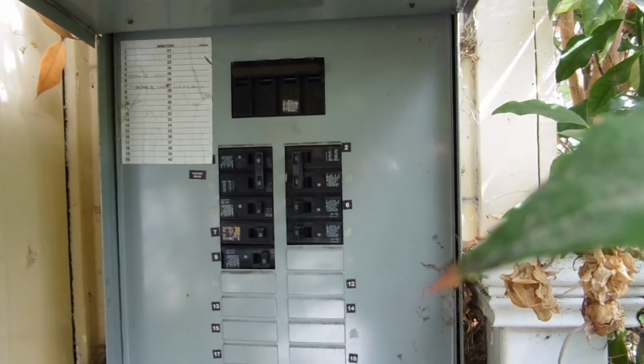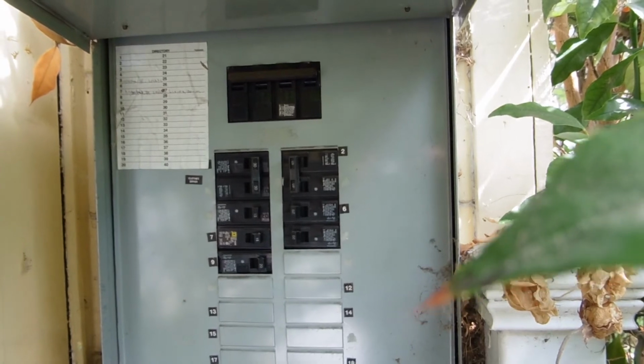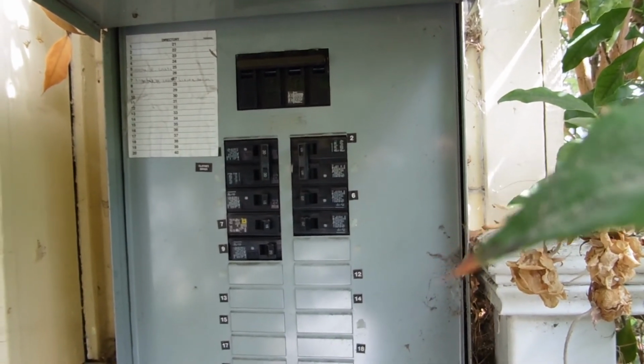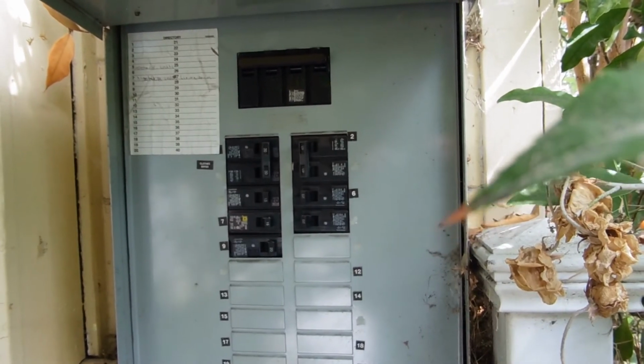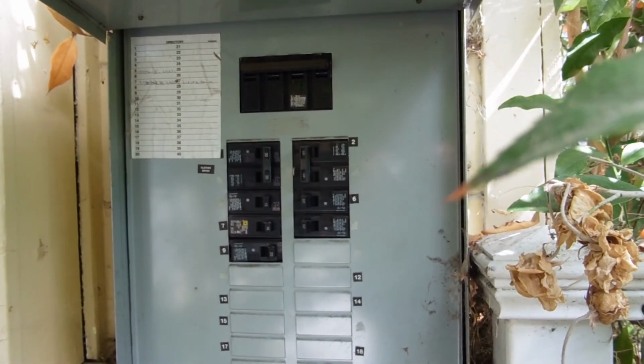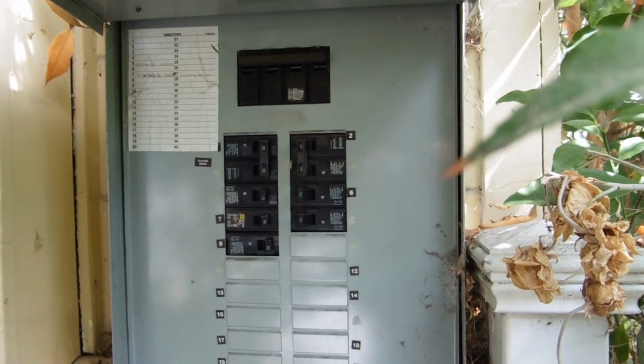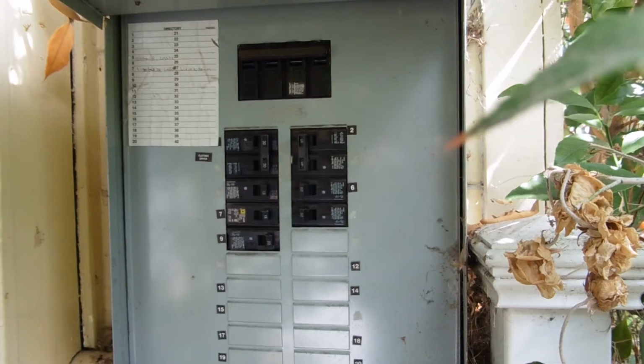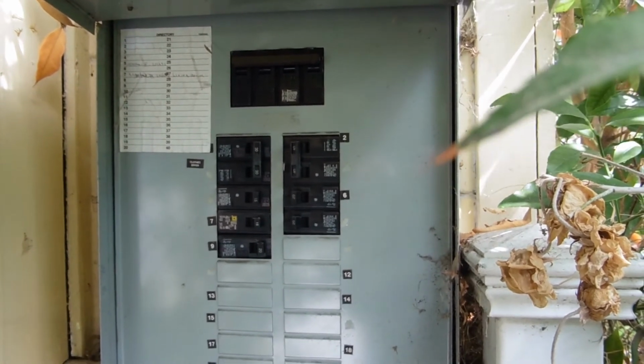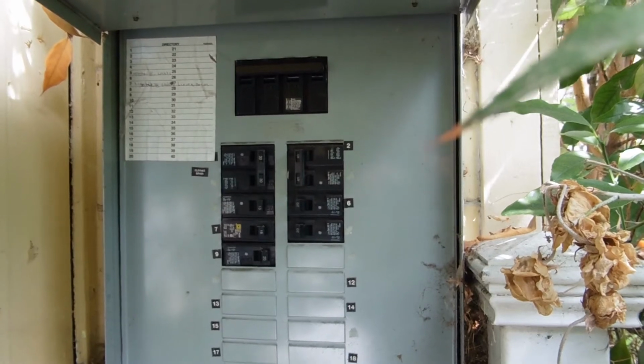So you can see there the numbers. There's one on the left that's 30, and then 15, then 15, then 20. And then on the right it's 40, and then 20, then 20. So that means two large circuits of 30 and then 40 amps, and then below that are 5 circuits of either 15 or 20 amps depending on the circuit. So the way you determine the capacity is first you look at the one at the top to find out how many amps it is, and then you add up the ones at the bottom to see the total that's assigned. So we have 70 plus 40 is 110, plus 30 is 140, plus 20 is 160 assigned. So we have 160 amps assigned on this service panel, and if I could see the rating on the top, I could tell if there was any remaining capacity.